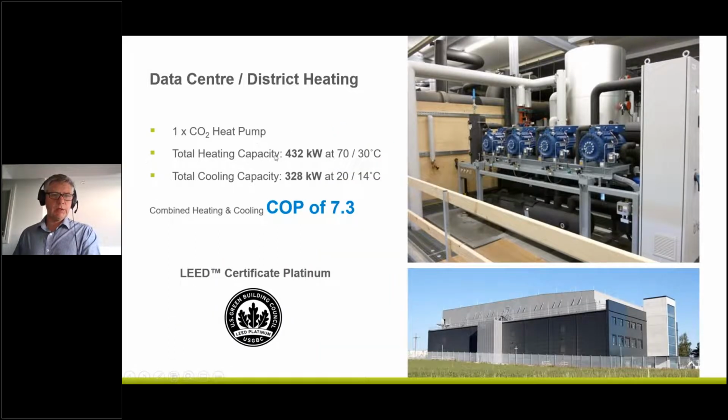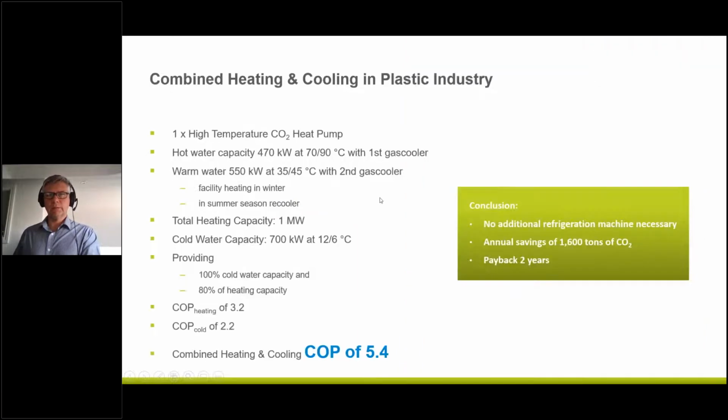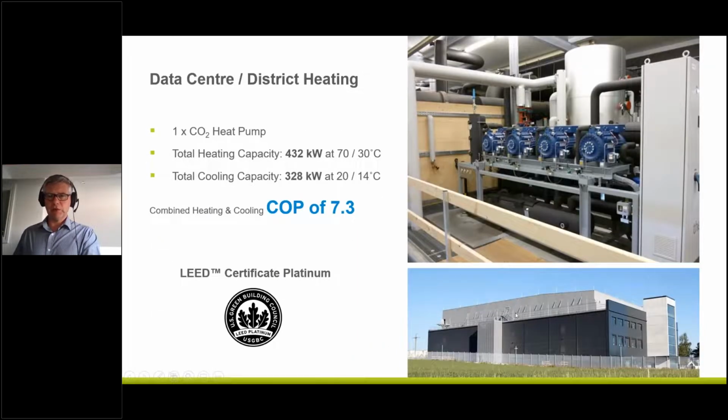This smaller unit here has 430 kilowatts of heating and just shy of 330 of cooling. And overall, a very impressive COP of 7.3. It's a LEED Platinum building. And yeah, this is during the installation there of the same.